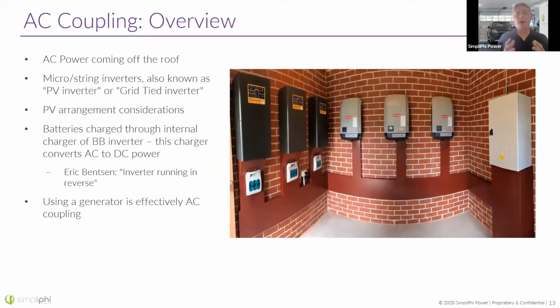Give an overview of AC coupling. This is AC power coming off the roof. So you're probably a little confused here. Don't PV panels produce DC power? Yes, they do, but in an AC coupled system, you've got either a string inverter or a microinverter on each string of panels or on each panel individually, immediately converting that power to AC power.